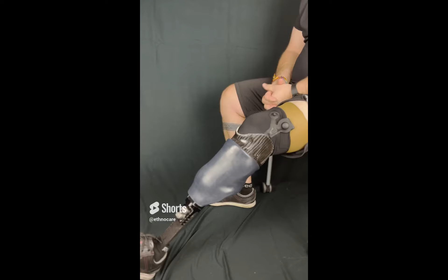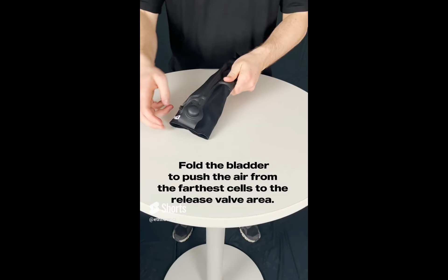Make sure your patient keeps their legs straight to allow better deflation. It's still possible to deflate the system without being in the socket, but you need to put pressure under the valve itself. It's also important to note that this image shows the user with a pin lock system. However, this device can also be used with most other suspension methods, such as vacuum systems and suspension sleeve systems.